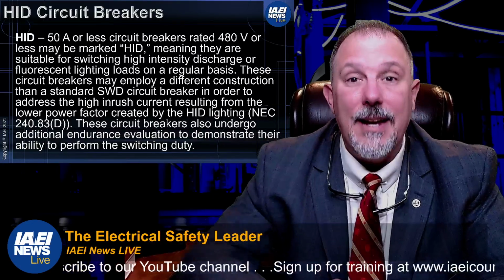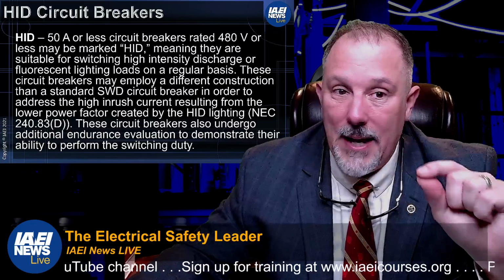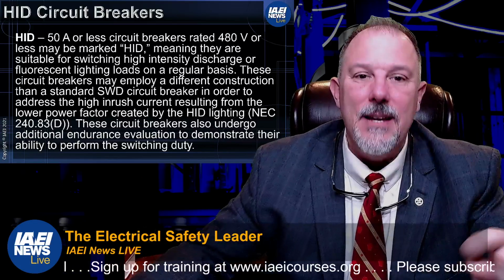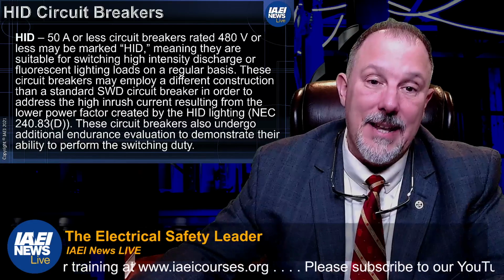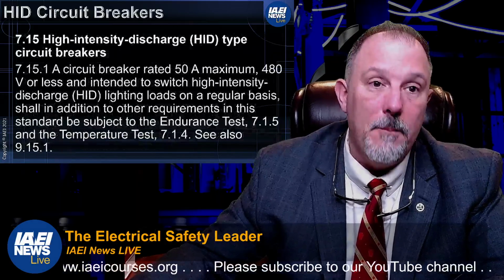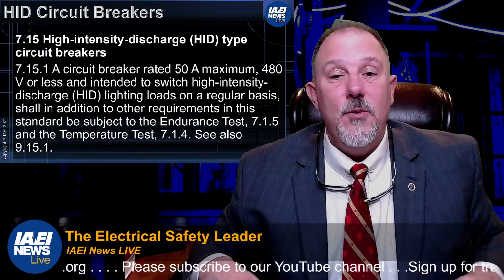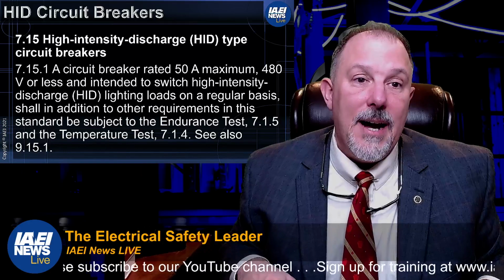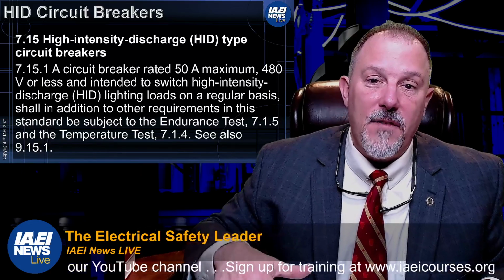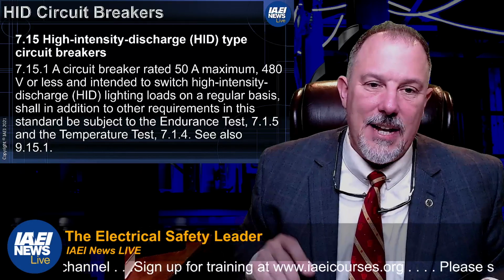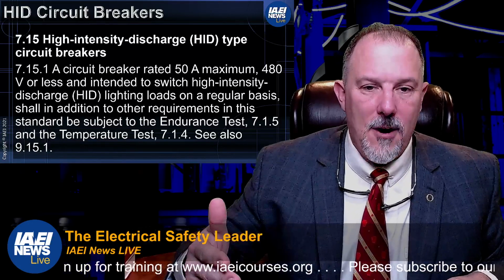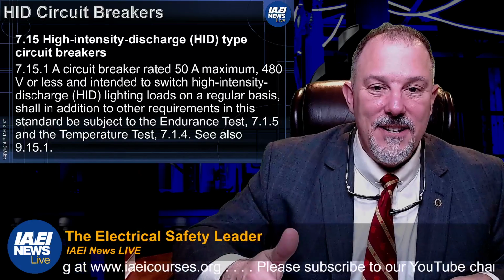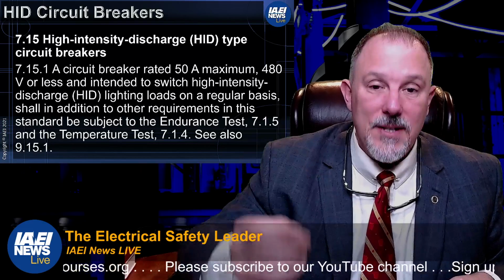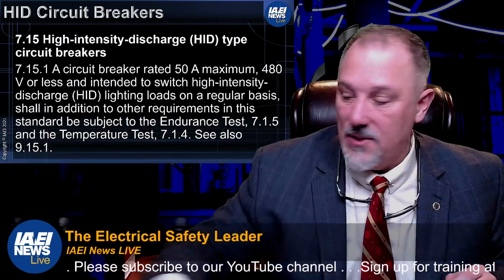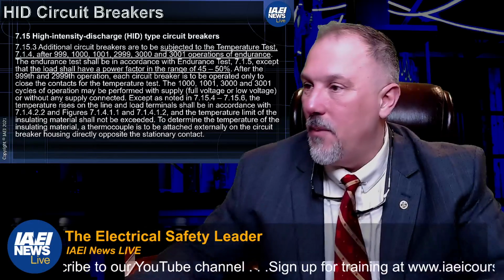We test them for the number of operations, but that's the fundamental difference in how that breaker is tested. And oh, by the way, because it's marked HID, it's also the breaker that you would use for fluorescent lighting loads when you're switching them on a regular basis. So if I go to the UL standard 489 for circuit breakers, high intensity discharge lighting type circuit breakers: a circuit breaker rated 50 amps or less intended to switch high intensity discharge lighting loads on a regular basis has to go through other requirements and be subjected, in this standard, to endurance tests 7.1.5 and the temperature tests. Okay, so here's what 7.1.5 tells us.